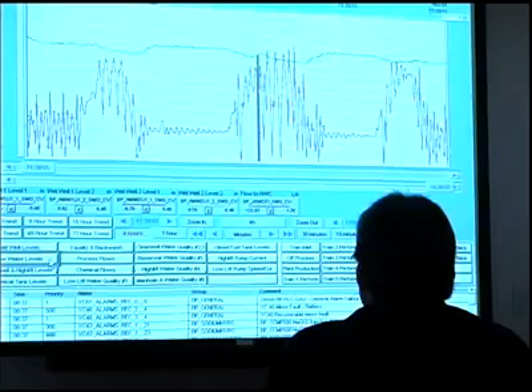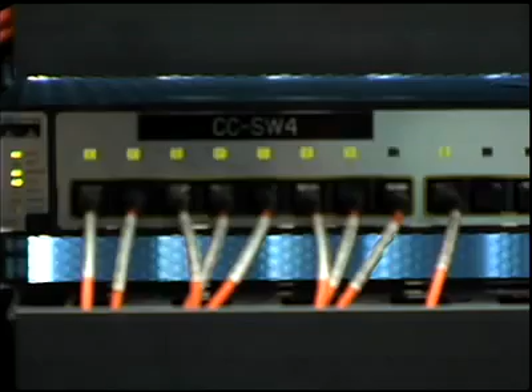BearPoint's operation is controlled by a Microsoft Windows system utilizing Wonderware terminal services to run the entire plant. Redundant servers with UPS backup systems log over 5,000 points of data 24 hours a day, 7 days a week. On the network side, redundant switches and redundant fiber optics talk DeviceNet and to 10 PLCs in the field. Once this information reaches the network closet, it gets routed into the I/O servers. All that information goes into the SCADA system, providing real-time data acquisition as well as controlling the plant through operator terminals in the control room.